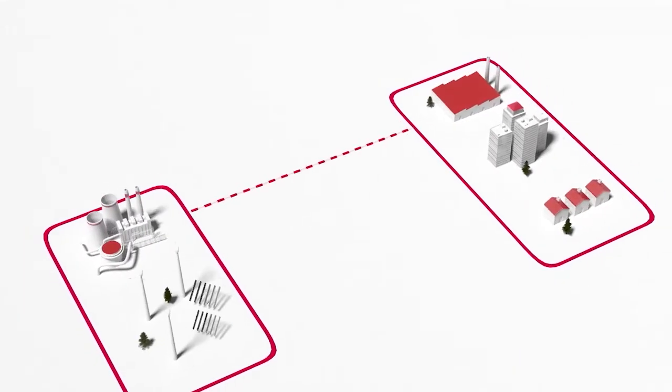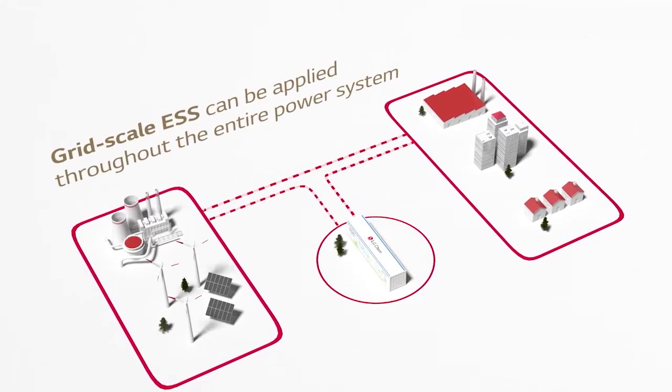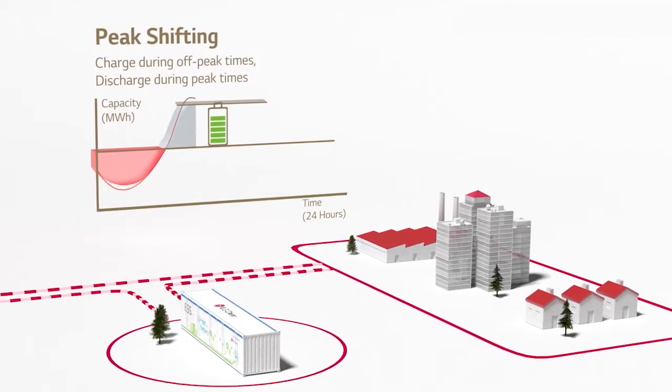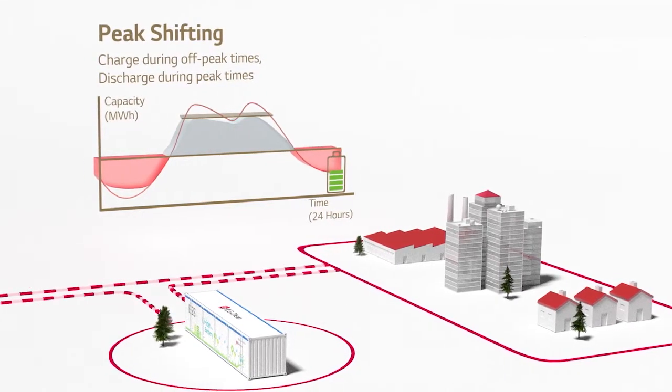The ESS, or energy storage system, is a system that can store energy. Most energy storage systems are basically huge batteries. We simply connect the batteries to the power grid. When grid-scale batteries are deployed, they provide capabilities through applications such as peak shifting. This offsets the need for additional conventional base load generation to serve peak loads by charging the battery during off-peak times and discharging during peak times. Using renewable energy or more efficient conventional generators to charge batteries reduces fuel costs and lowers emissions.